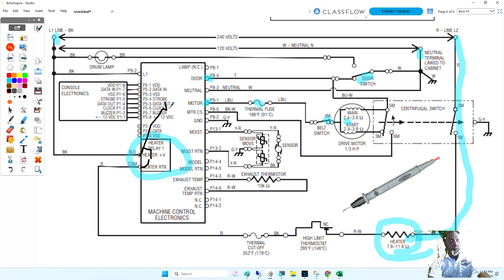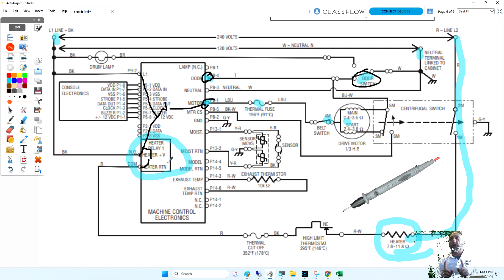No. So either this line 1 not only feeds a switch here for the relay on the heater, like when the board comes on, the switch closes. This can also go to the board to another relay here, or it can feed line 1 here, and there's another relay that's not drawn there. So if I don't have 120 on P84 and P91, my door switch could be bad, or a broken wire here. But there's a relay on the board, don't forget it. So we have 2 ways we have to go.